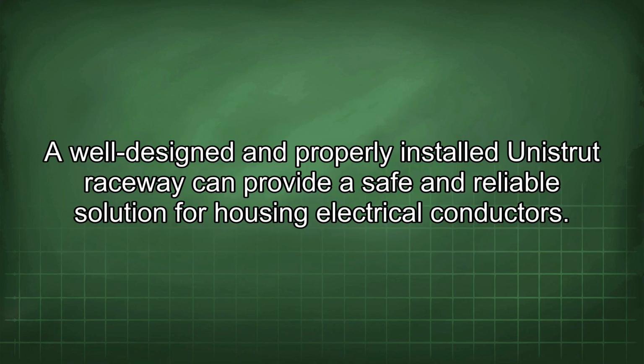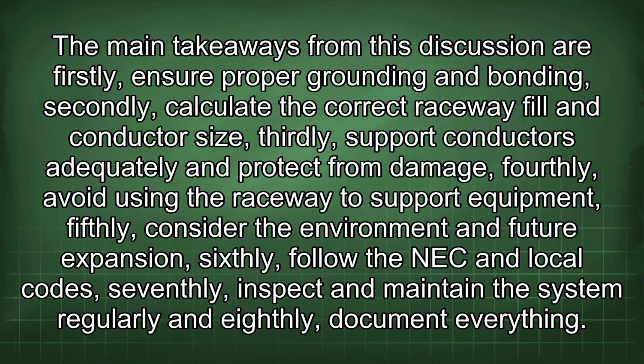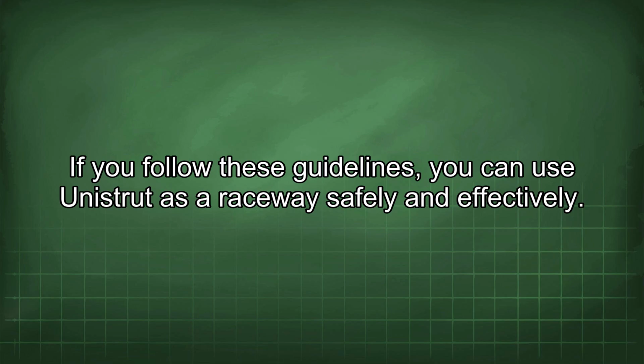A well-designed and properly installed Unistrut Raceway can provide a safe and reliable solution for housing electrical conductors. The main takeaways from this discussion are: firstly, ensure proper grounding and bonding. Secondly, calculate the correct raceway fill and conductor size. Thirdly, support conductors adequately and protect from damage. Fourthly, avoid using the raceway to support equipment. Fifthly, consider the environment and future expansion. Sixthly, follow the NEC and local codes. Seventhly, inspect and maintain the system regularly. And eighthly, document everything. If you follow these guidelines, you can use Unistrut as a raceway safely and effectively.